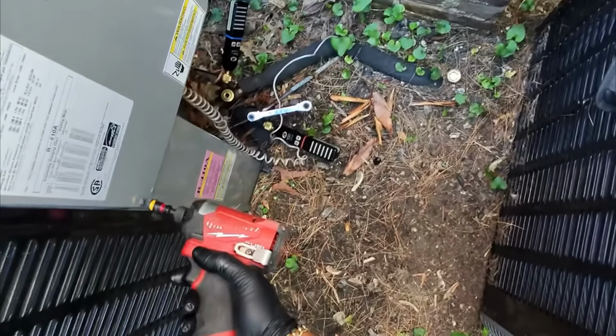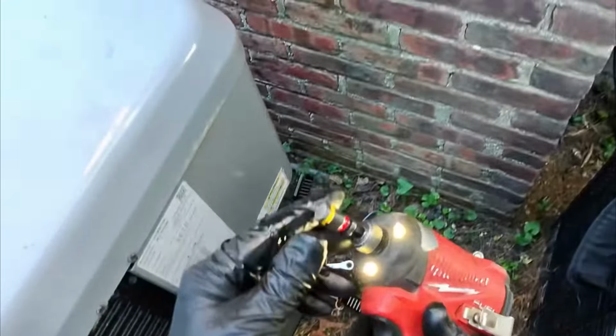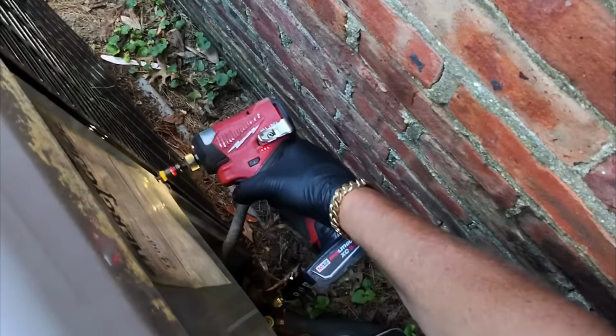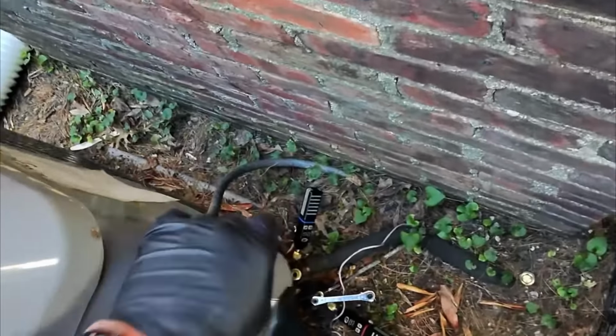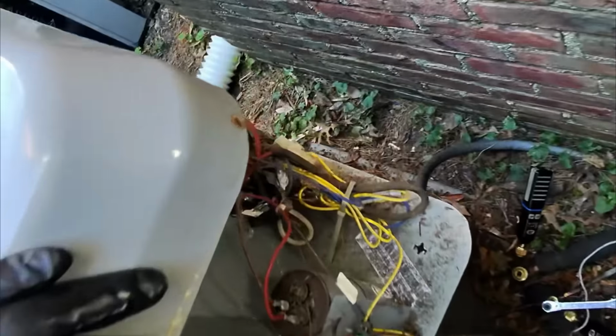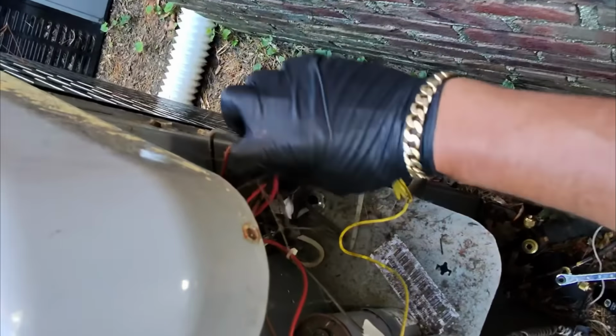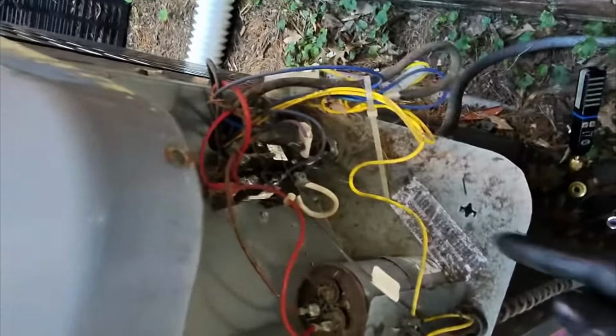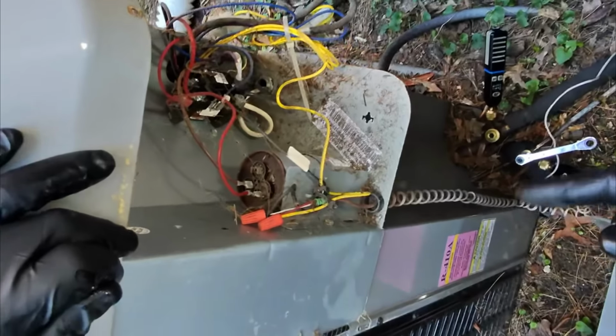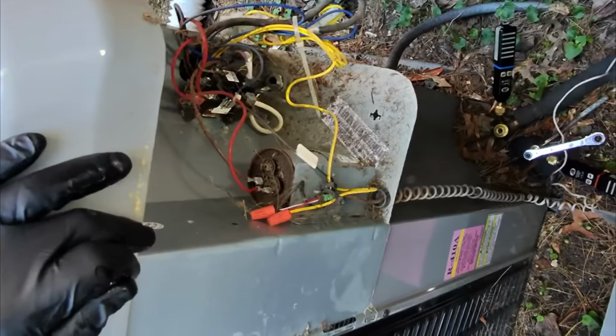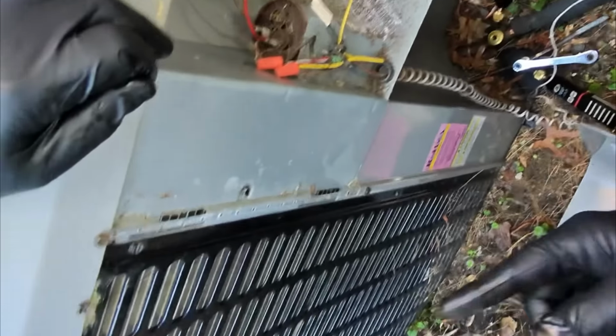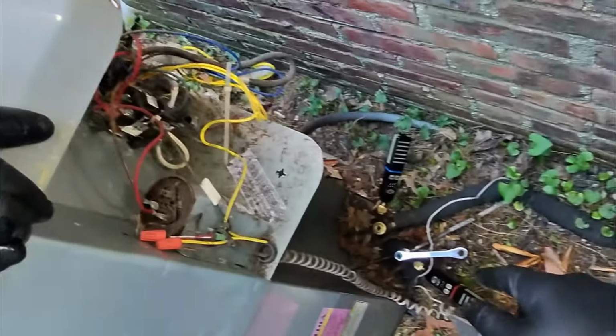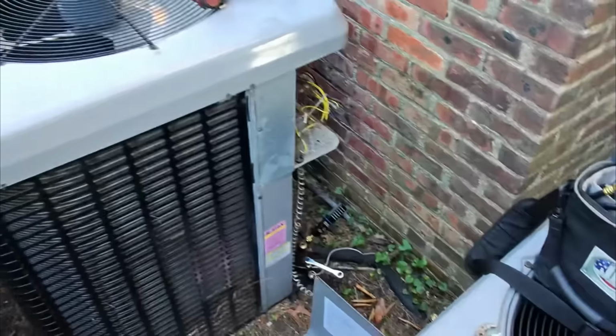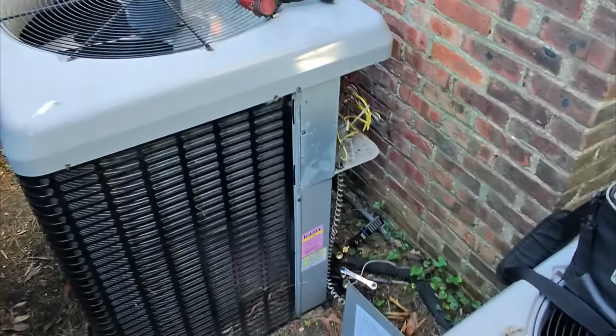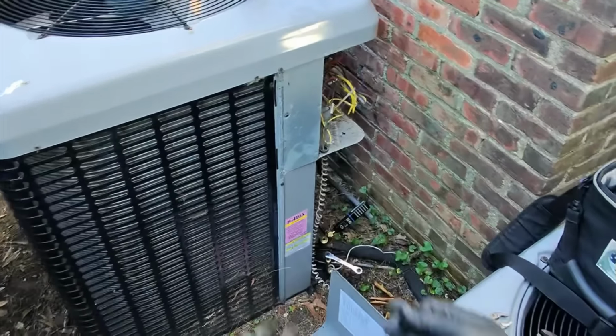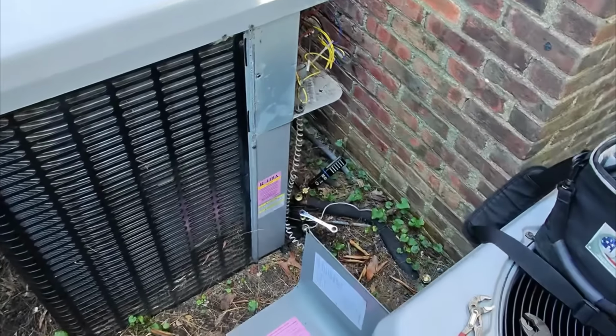Got my probes on the high and low side. Let's pop the electrical panel off. Our contactor is protected behind that little plastic piece. I want to remove that so I can push in the contactor and fire up the outdoor unit, sucking the refrigerant down into the condensing coil. That'll save me time from having to recover the R410A refrigerant in the system.